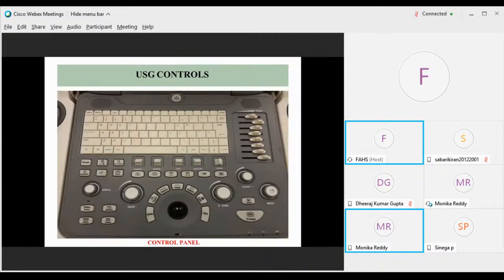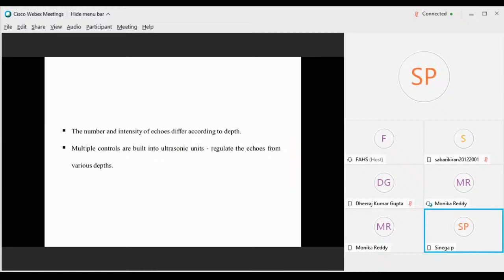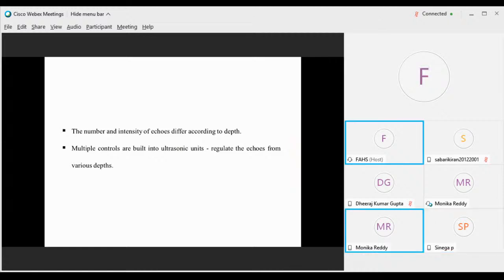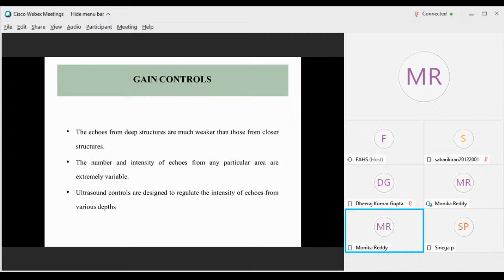Now come the USG controls. This is a control panel on which we can manipulate the controls to get a better image quality. There are a number of echoes and intensities. Multiple controls are built into ultrasonic units, which regulate the echoes from various depths. That's why we are using gain controls.